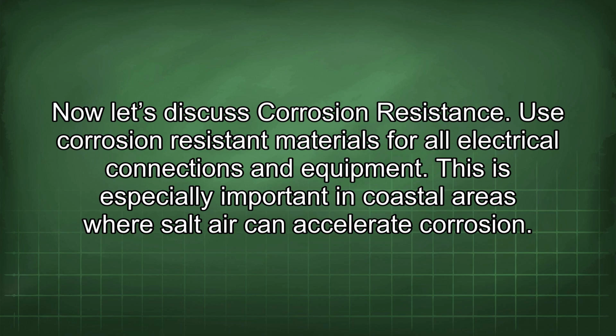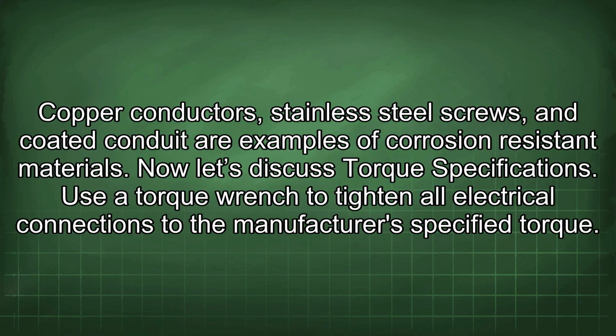Now let's discuss corrosion resistance. Use corrosion-resistant materials for all electrical connections and equipment. This is especially important in coastal areas where salt air can accelerate corrosion. Copper conductors, stainless steel screws, and coated conduit are examples of corrosion-resistant materials.